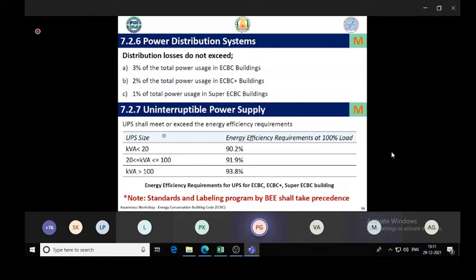And UPS, like your lighting UPS or your system UPS, all the UPS should comply with the minimum efficiency, which is 90.2%. Again, depending on the capacity, it varies from 90 to 94%. So this again should be specified. And whenever there is a star labeling available for UPS, then that will take precedence over these values.